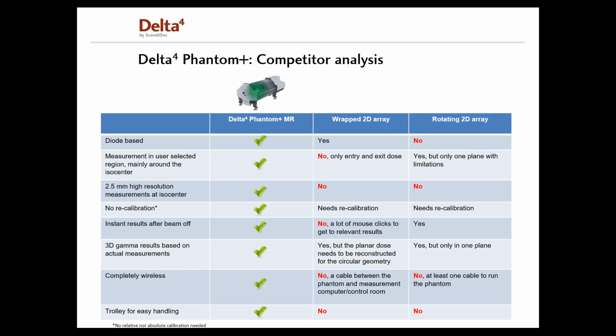Also here we have competitor analysis where we are comparing the Delta4 Phantom Plus with a wrapped 2D array and a rotating 2D array. So to compare diodes with ionization chambers, ionization chambers have relatively large volume, potentially resulting in a loss of accuracy due to the volume averaging effect, which is a characteristic for ionization chambers in modulated fields. And to actually measure in the target and steep dose gradient regions provides real measurements with the highest accuracy. The Delta4 Phantom Plus has the highest resolution on the market. And with our highly stable detectors, the Delta4 Phantom Plus requires no relative recalibration.